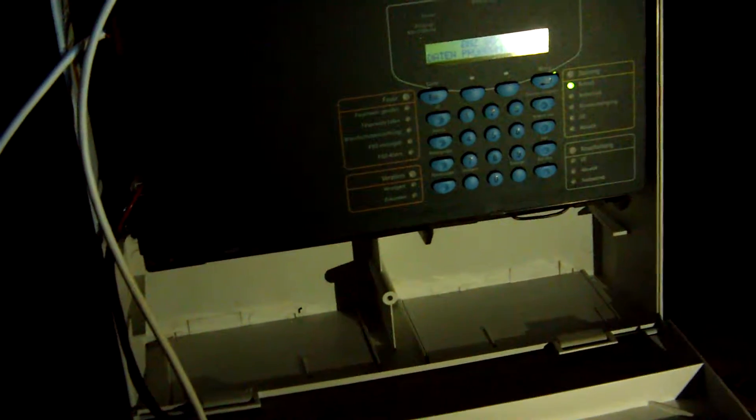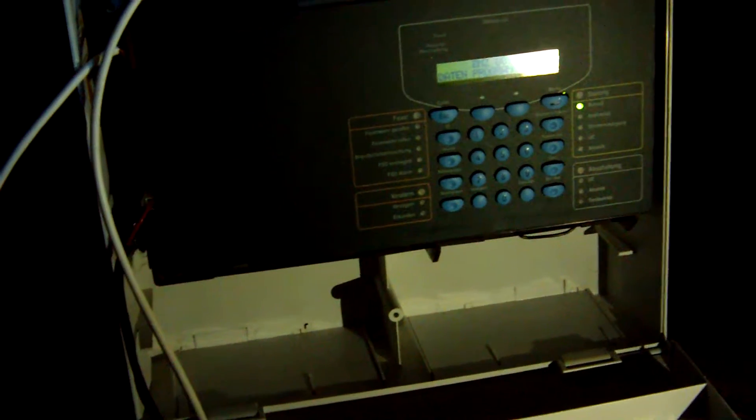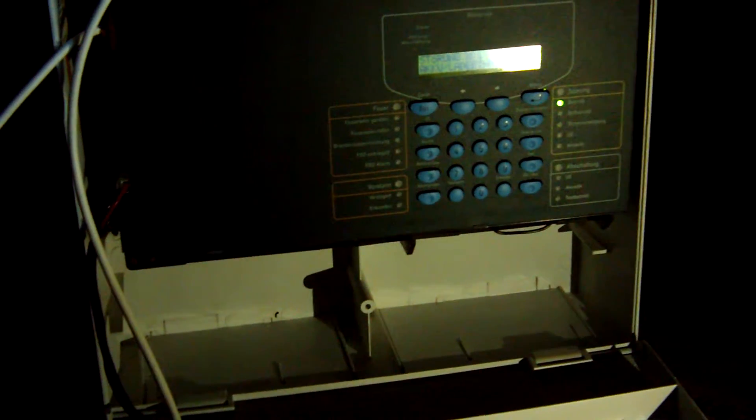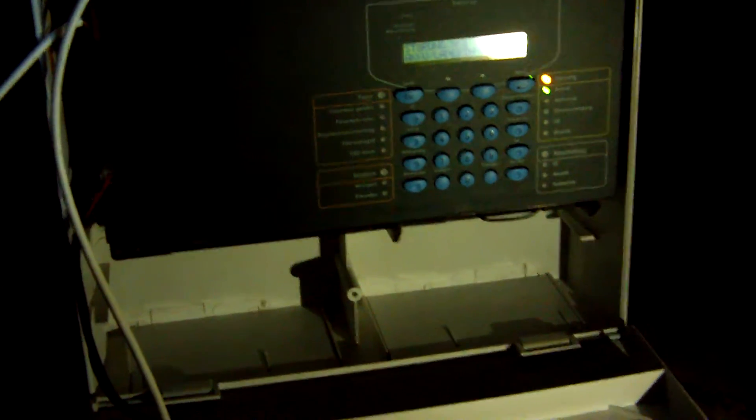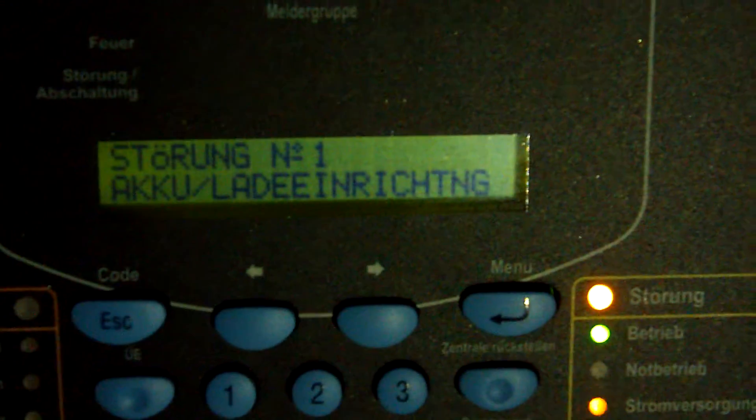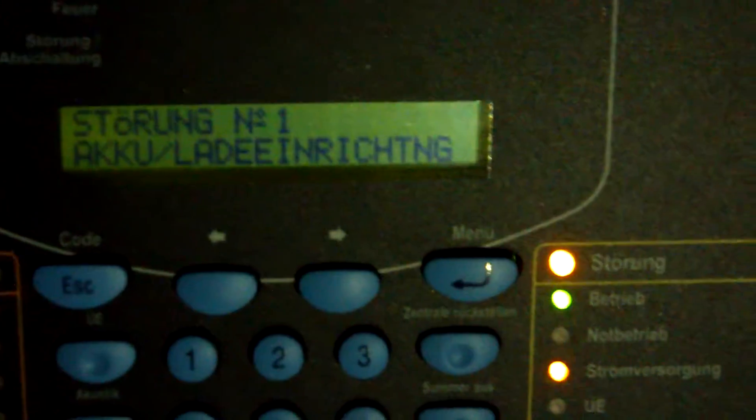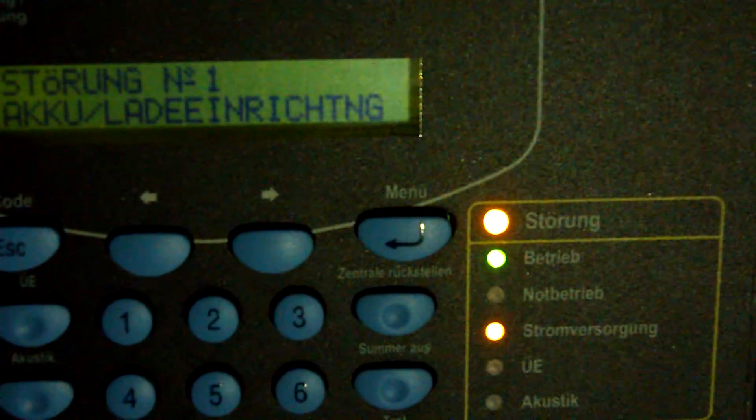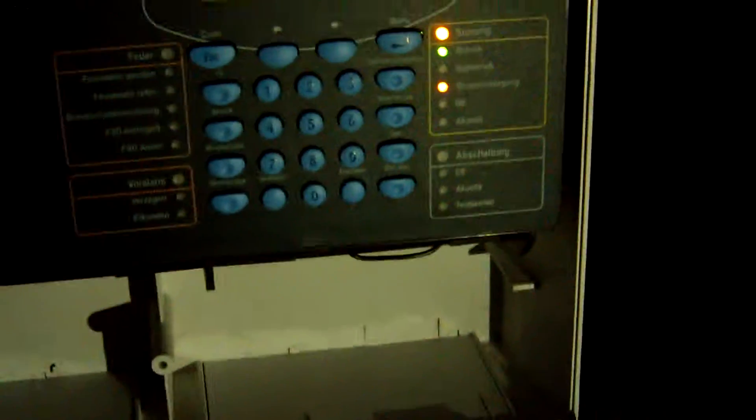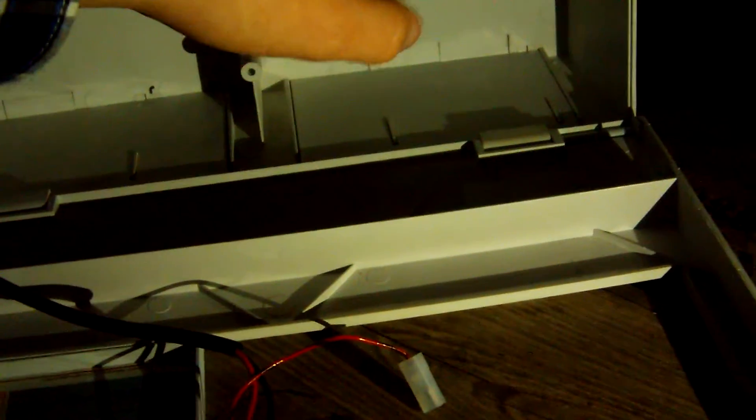So this fire alarm panel is by the German manufacturer Esser, it's a company by Honeywell. And I'm getting the first error message. That's the first error message saying that there's something wrong with the power supply, with the emergency power supply, because I don't have any batteries in there.